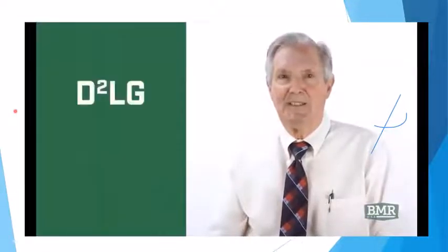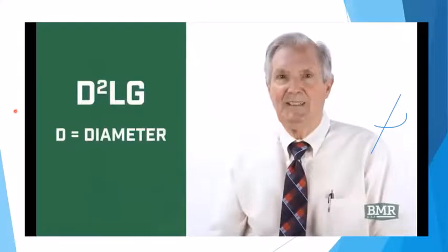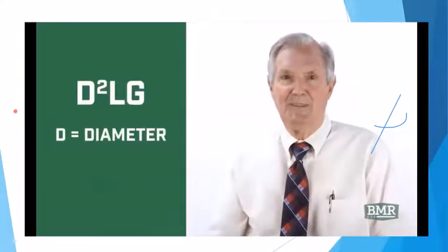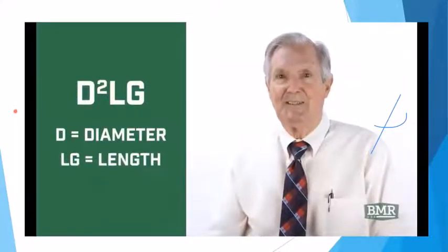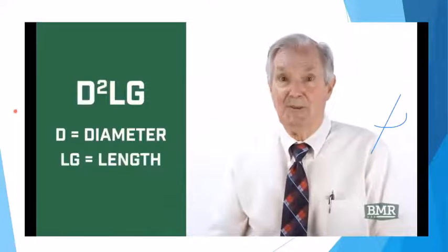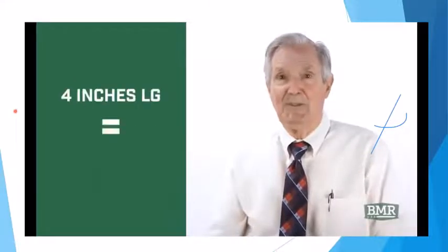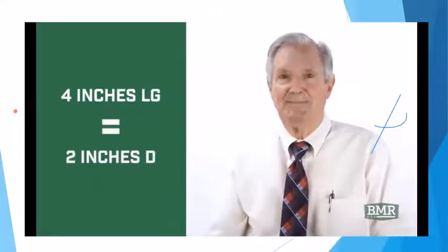To illustrate this design preface, let's look at basic design characteristics. The output of the motor is directly a function of D squared Lg, where D equals the diameter of the electrical core and Lg the length of the electrical core. So 4 inches in core length can be duplicated with 2 inches in diameter.